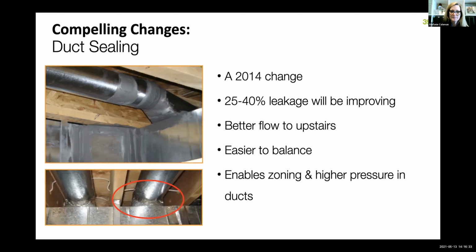Sure, I would say if the builder's not doing a blower door test, then pick a number and say to the builder, if you're the designer, look, I've designed this at 3.5 air changes because that's what the code says you should be at. If you're not, then it's on you. If it's higher than that, I'm designing for that. That's literally what you'd write down on your information sheet. There is a sheet in F280 that says, here's all my design assumptions. I've assigned 3.5 because the code says you should be at 3.5. That's why builders need to be blower door testing houses.